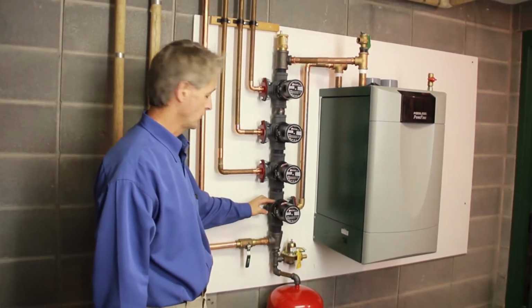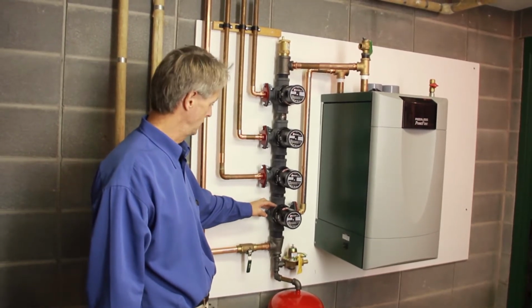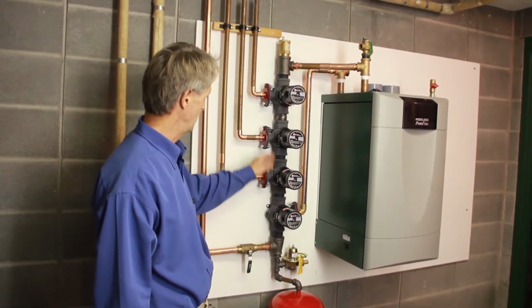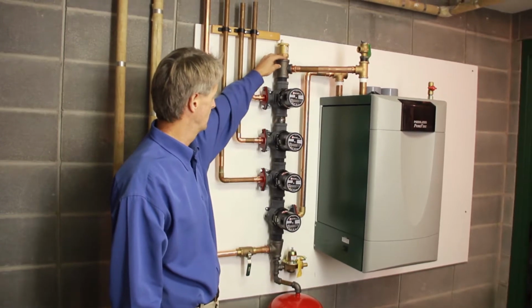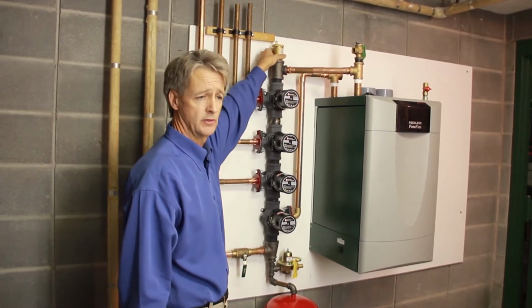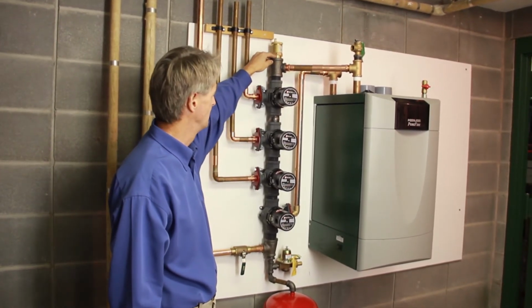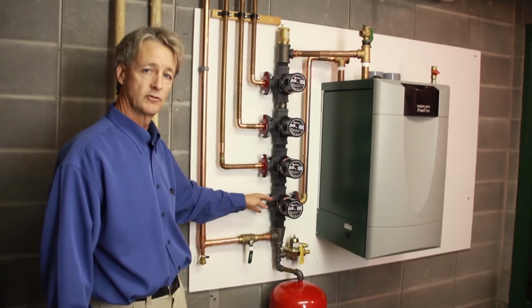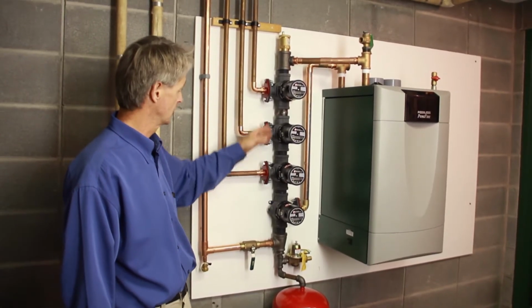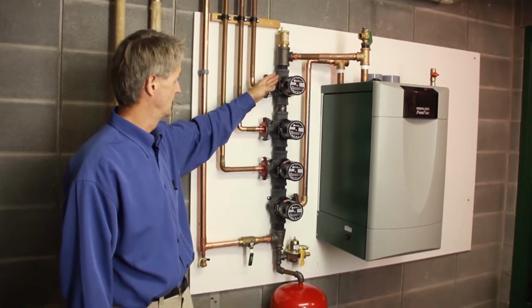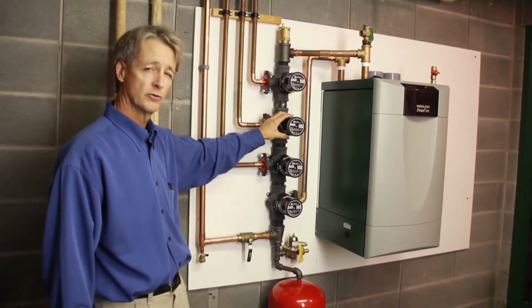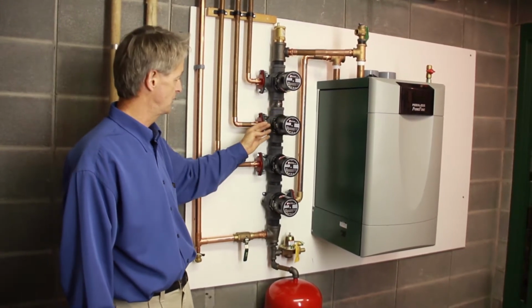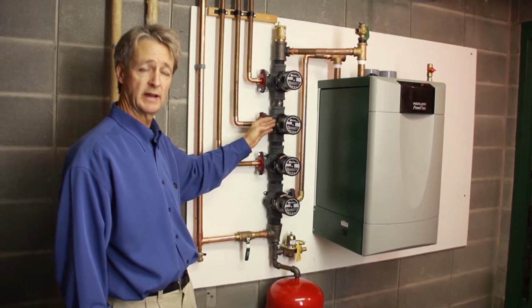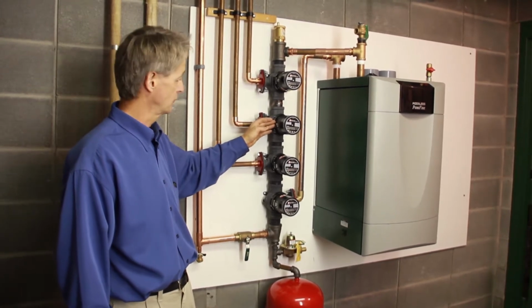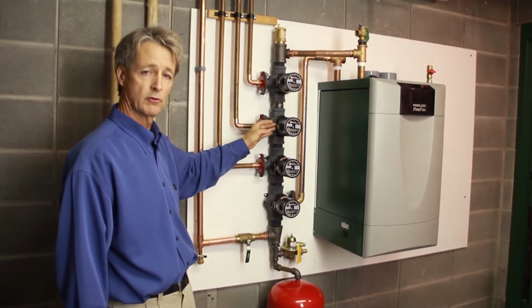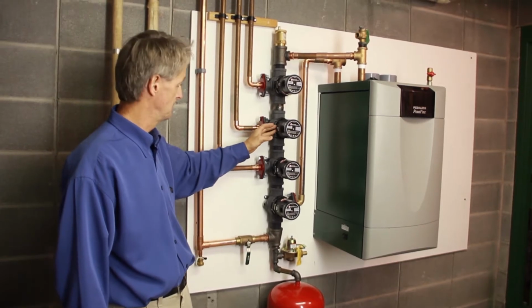Any air that returns from the circuits, the zones, enters the common pipe and migrates to the top of the common pipe and is vented through the 1.5-inch vent we have on the top. Testing has shown us that installing the common pipe vertically and affixing the pump horizontally, allowing the impellers to draw water off the side of the common pipe, gives us a system that's very resistant to air binding.